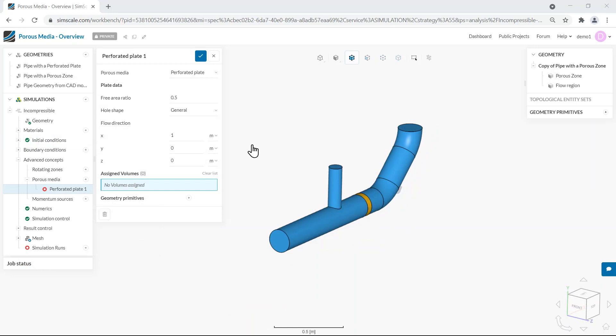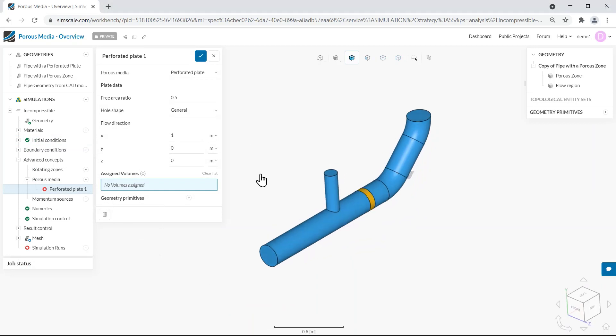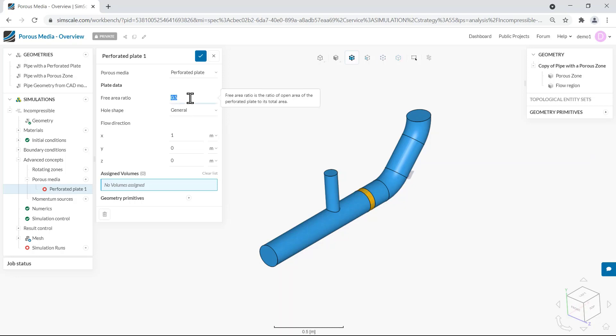First let's check the setup of the perforated plate model. The perforated plate porous media model is going to be optimal whenever you have a perforated plate and you don't have any experimental data about the expected pressure losses. The first setting is the free area ratio, which represents the ratio between the open area and the total area of the plate. This value will always be between 0 and 1. In my case the free area ratio is 17.6 percent.